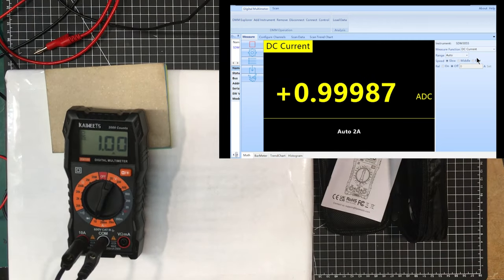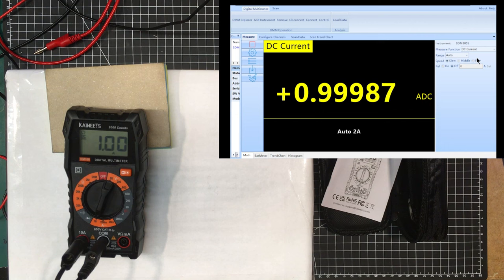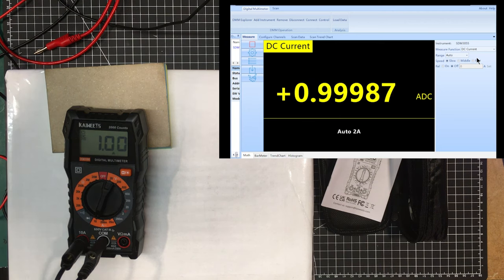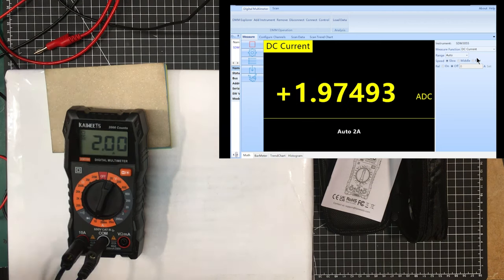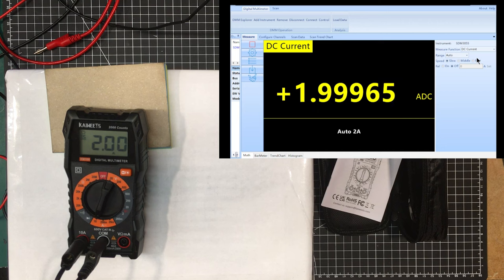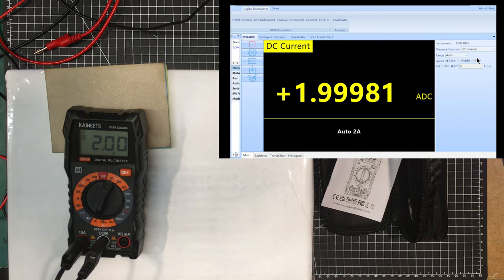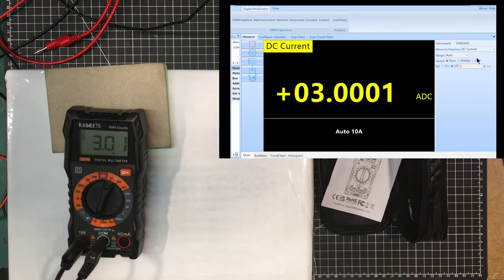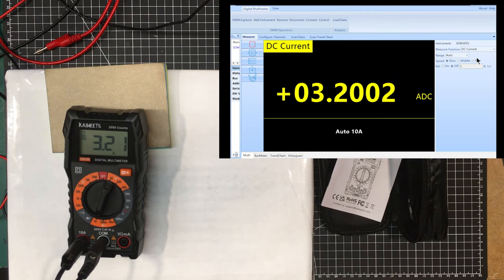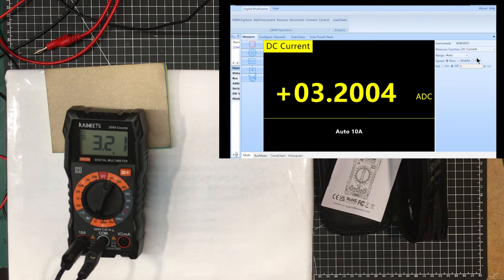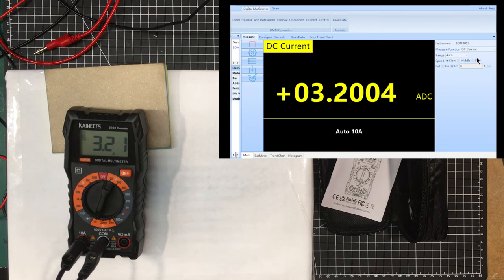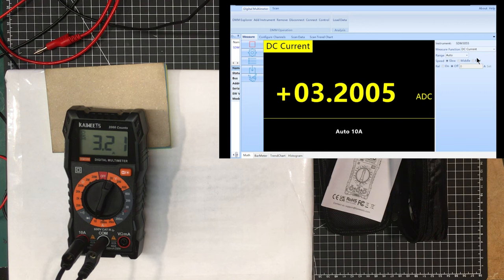Let's go try the 10 amp scale. We got one amp going into it and the Siglent reading 0.99984, so that's perfectly okay. Let me up this by another amp. Siglent saying 1.9999, this is saying 2.0. I think we can't get much higher than 3.2, so let's try that. 3.2002 going into the Siglent, 3.21 on this. That all looks pretty good. There's no smoke coming out of it either, which is all really good.